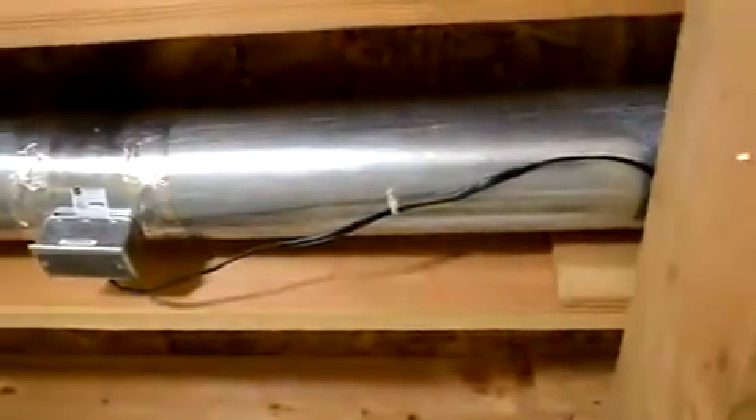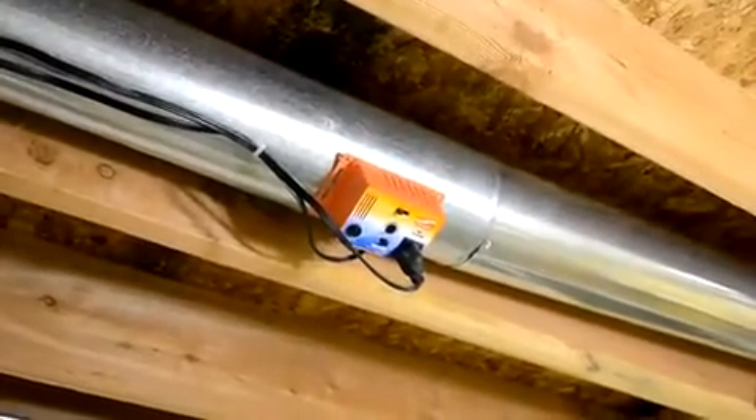Locate the position between the inline duct fan and the register where you wish to mount the Ductstat. Mount between 1 and 10 feet downstream from the inline duct fan. Tape the supplied template to the air duct to mark the mounting holes to be drilled. Drill a hole in the air duct for the air intake hole shown on the template.